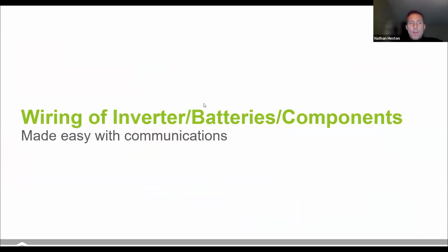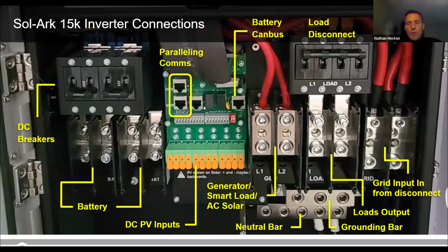All right, so combining battery banks is important. Let's talk about wiring. So in a Sol-Ark 15k, you have a section on the left side of the inverter for DC inputs. The DC inputs, you've got 2 positive inputs. Both of those positive inputs have their own individual breaker and then are combined on a common DC bus after the breakers. So this is a nice option. You can actually use the dual DC inputs on a Sol-Ark 15k as a battery combiner for 2 stacks with individual 200 amp overcurrent protection on both of your inputs.